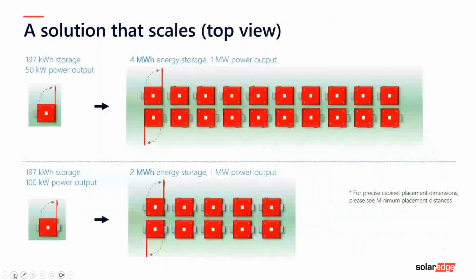And this is what you can have, two solutions here. You can have one inverter on each battery cabinet, which gives you 4 megawatt hours with 1 megawatt of output. Or you can have 2 megawatt hours of energy storage and 1 megawatt of output, because you've got 100 kilowatts on each one as opposed to 50.